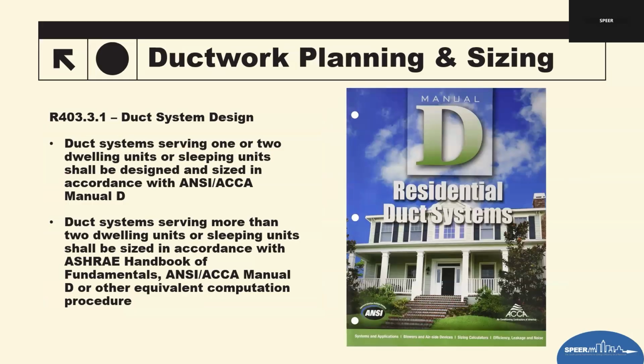Ductwork planning and sizing, we just talked about it a second ago, but Manual D is now required. The 2024 is basically saying that ducts need to be designed and sized using nationally recognized engineering methods, not rule of thumb. Back in the day, and even probably today, we're still doing oversizing of systems and undersizing of ductwork, and it shows that it does not meet the airflow or air balances that we need inside the home. So even though code still says all the way to the 21 Manual J and S, in the 24 we now include the Manual D. So this section of the 24 tells how the system must be designed, not just installed. The goal is to ensure airflow is balanced, so equipment is properly matched and the system meets comfort and efficiency expectations.